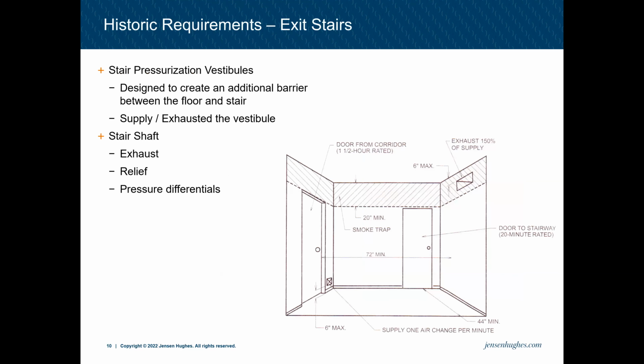And throughout the years, these types of systems have had different historic requirements. So stair pressurization used to have exhausted vestibules that would be in front of the entrance to our stairs on each level. They were designed to create an additional barrier between the floor and the stair, and we would have a specific supply and an exhaust within the vestibule.